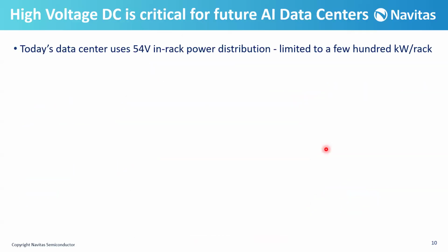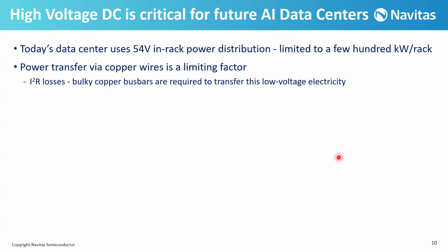Now let's look at this slide. This slide shows that high voltage DC is critical for future AI data centers. But why? Today's data center uses 54 volt in-rack power distribution, which is limited to a few hundred kilowatts per rack. It means that the power transfer is done by copper wires. And by this voltage, we need a high current in order to transfer. Bulky copper bus bars are required for this transfer, and obviously we have high power loss.